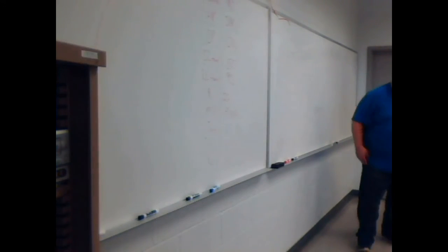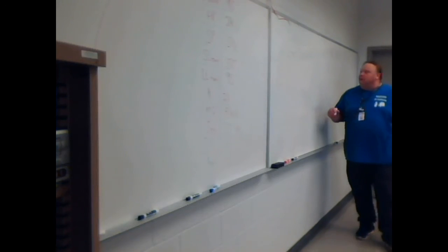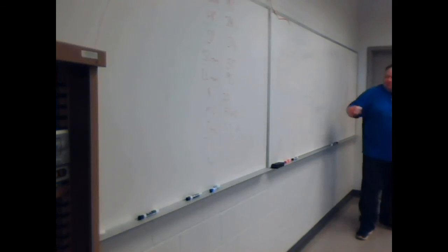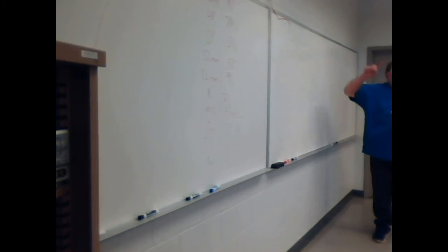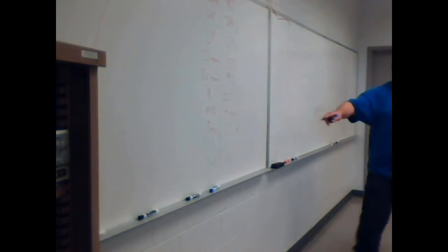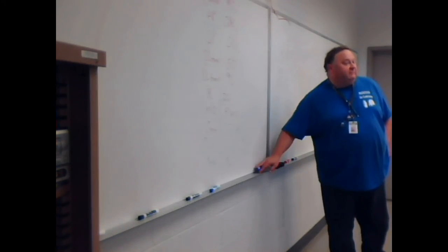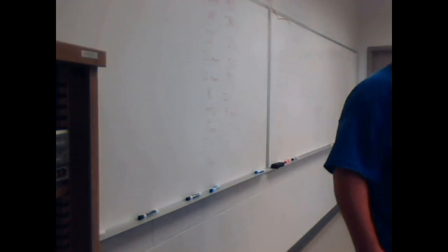Is that 16 amps? Yeah. So am I above or below what I expected? Does this match anything in your book? No. I got one question. Yes, sir. How did you get the amp draw again? We said 7 amps per ton, and I had a 3-ton system here. So 3 times 7. Although it's better to use the data on the plate if we got it.